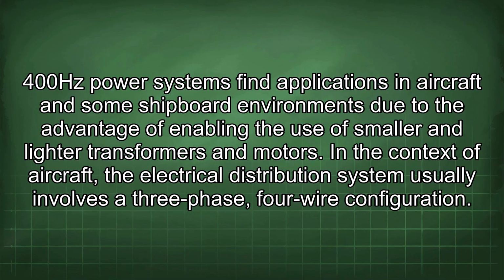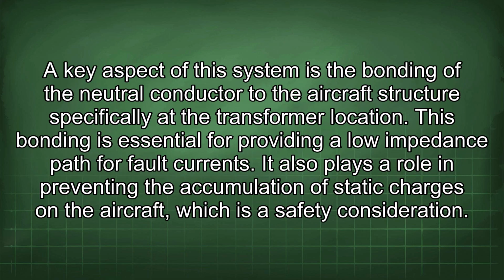400 Hz power systems find applications in aircraft and some shipboard environments due to the advantage of enabling the use of smaller and lighter transformers and motors. In the context of aircraft, the electrical distribution system usually involves a three-phase, four-wire configuration. A key aspect of this system is the bonding of the neutral conductor to the aircraft structure, specifically at the transformer location. This bonding is essential for providing a lower impedance path for fault currents. It also plays a role in preventing the accumulation of static charges on the aircraft, which is a safety consideration.